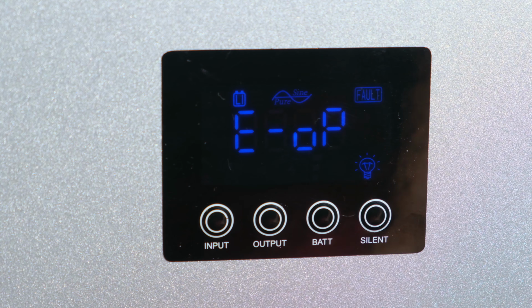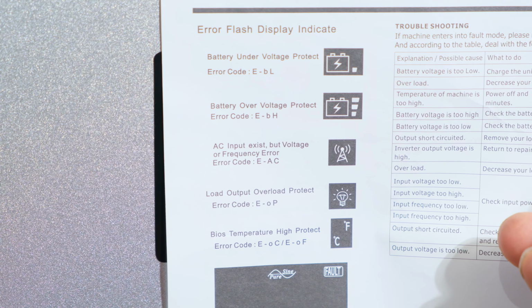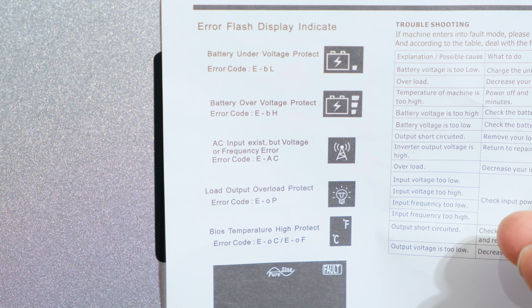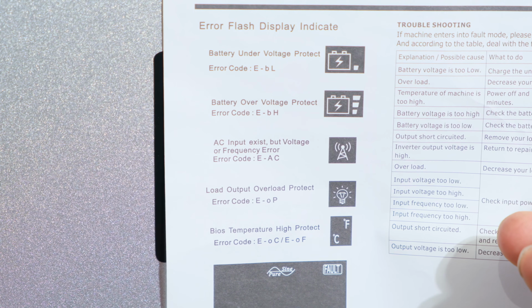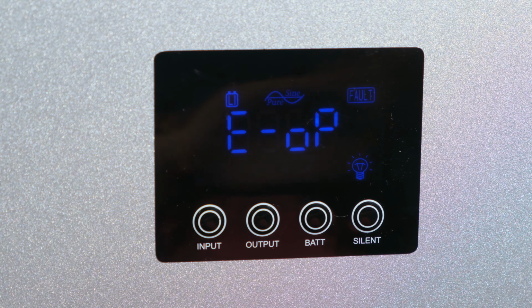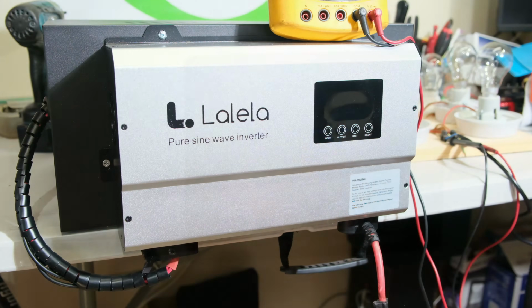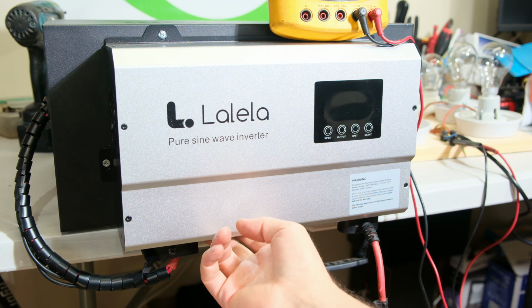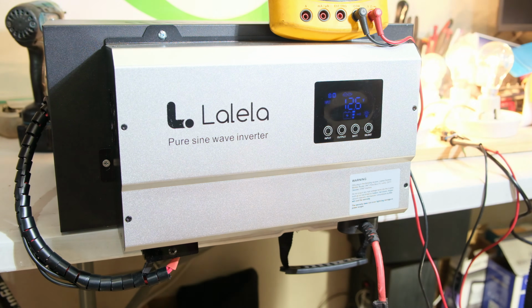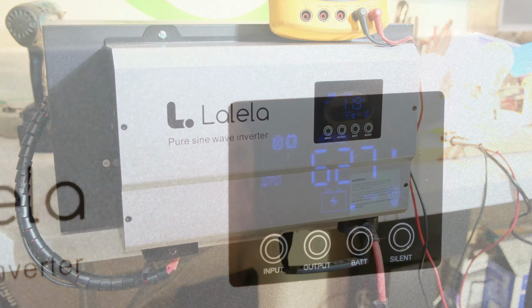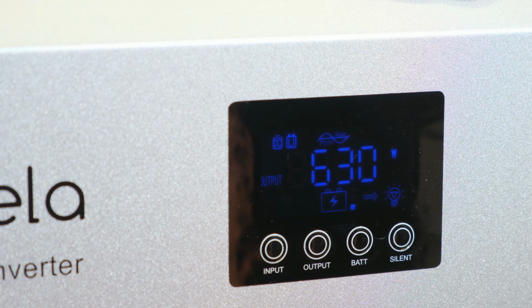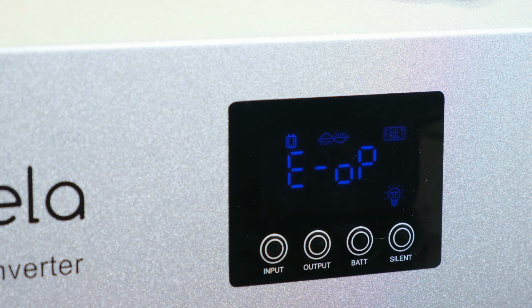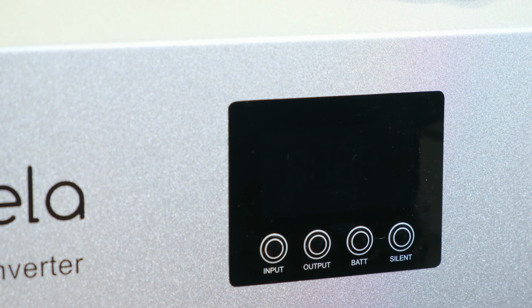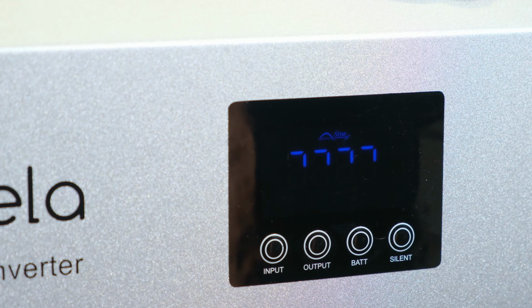It says EOP. Right, in the manual they show a few fault codes. In this case it is load output overload protection, error code EOP. So the instruction is to power down the unit completely and then restart it. Let's see if that functions correctly. Right, I've powered the unit down and let's restart it. Right, all the loads are back up and running, even though it is still overloaded, so it's actually pretty resilient. The inverter side of this unit is good, but it did go into overload again. So I'm going to power it down and switch it back on and let's see what happens.